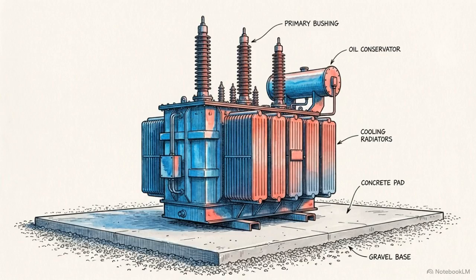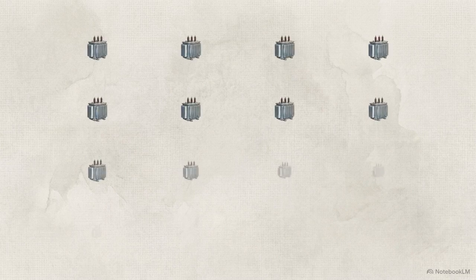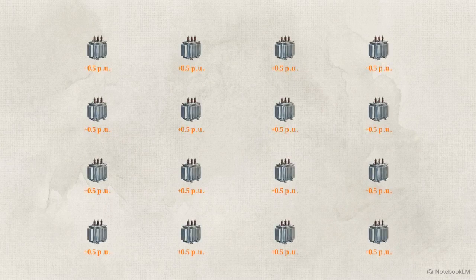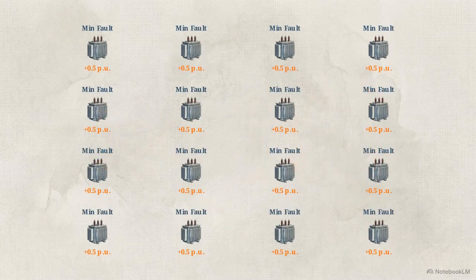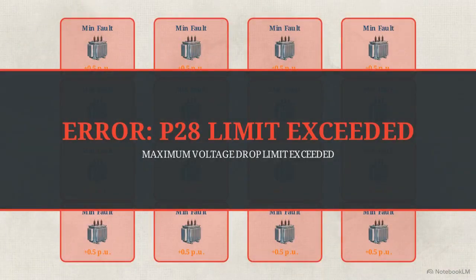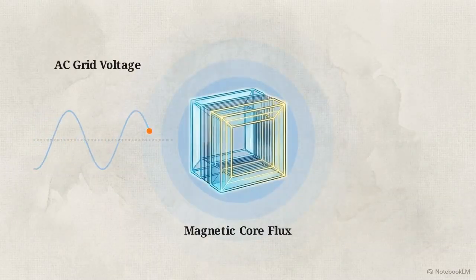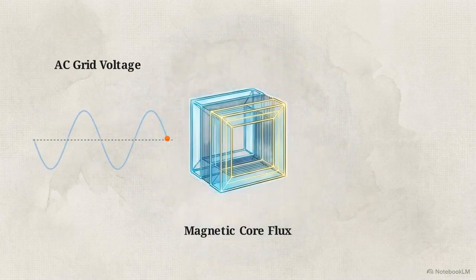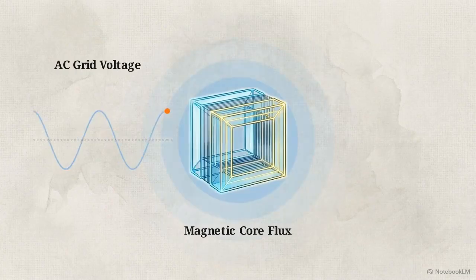Modeling a simple transformer under these parameters ensures a wide margin of safety for the grid. However, when applied to a large site with dozens of transformers, these compounded assumptions create a mathematical roadblock. The P28 standard acts as a rigid gatekeeper. You either prove your site meets the envelopes under these exact conditions, or you don't connect. To understand why compliance is so difficult, we need to look inside the magnetic environment of the transformer core.